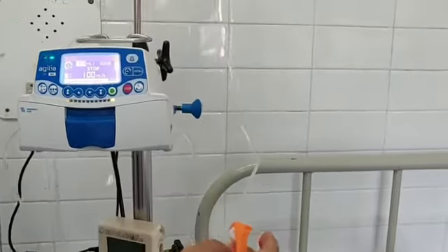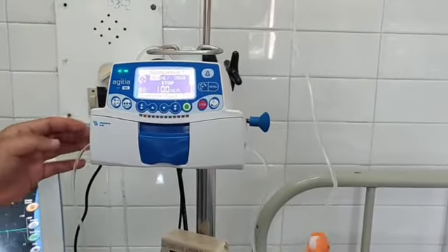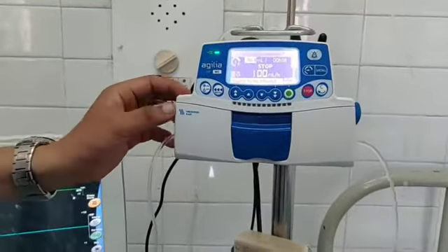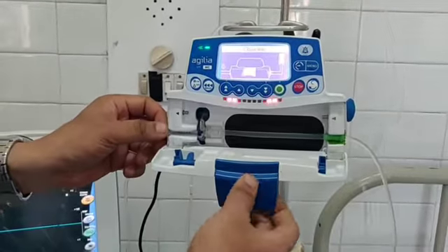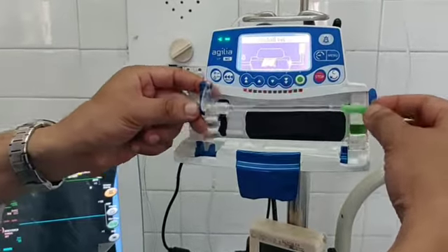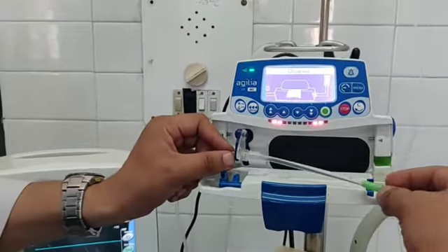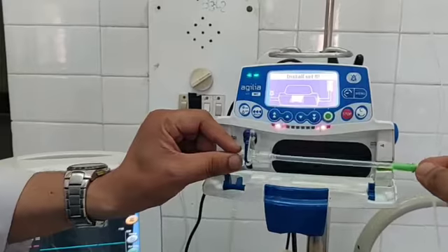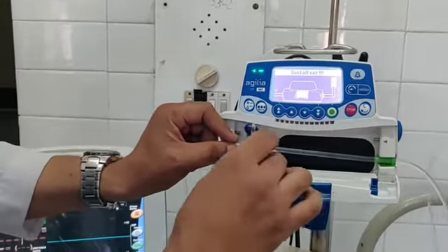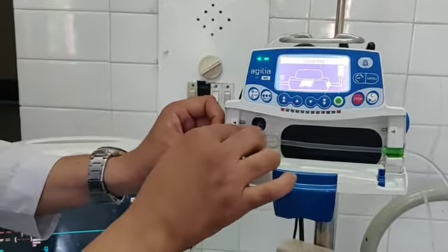And I have positioned it on the stand, and it is connected via the burette line. Since this infusion pump only supports the pump-specific burette line, that line is taken. In this there is a green tubing, which is the site of insertion, and there is a triangular knob, which is for the pressure line.